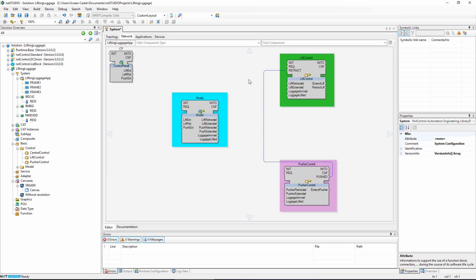NxtStudio uses a concept called symbolic links to achieve interacting with the actual IOs. Without spending too much time explaining what this is, I think giving an example and showing how to do it will clarify this. To first add input blocks that create symbolic links, we shall add a block called symlink multivariable destination. Okay, this one, and you add that here.